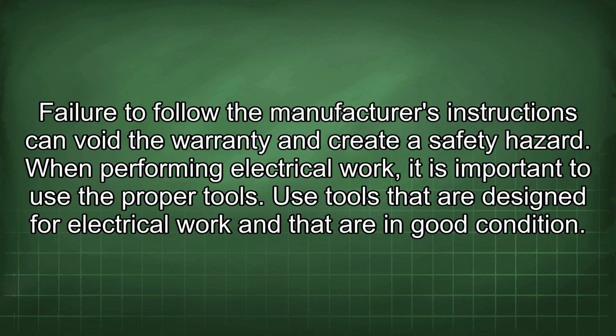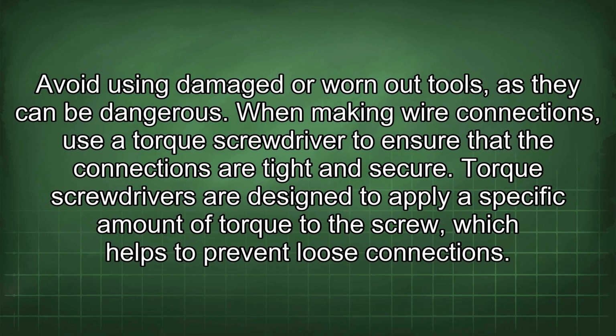When performing electrical work, it is important to use the proper tools. Use tools that are designed for electrical work and that are in good condition. Avoid using damaged or worn-out tools, as they can be dangerous. When making wire connections, use a torque screwdriver to ensure that the connections are tight and secure. Torque screwdrivers are designed to apply a specific amount of torque to the screw, which helps to prevent loose connections.